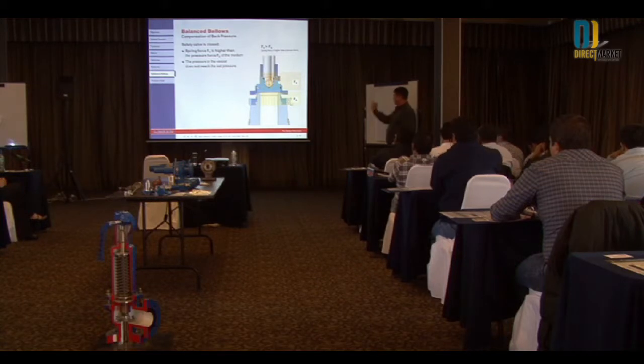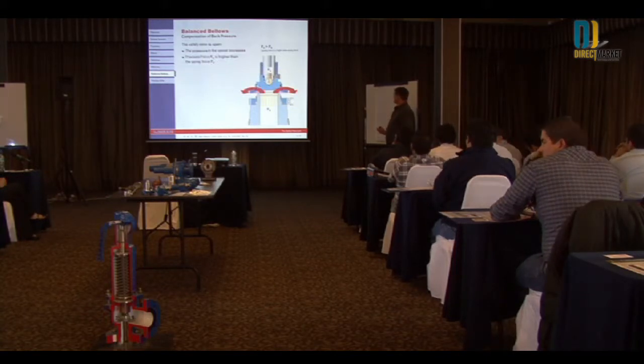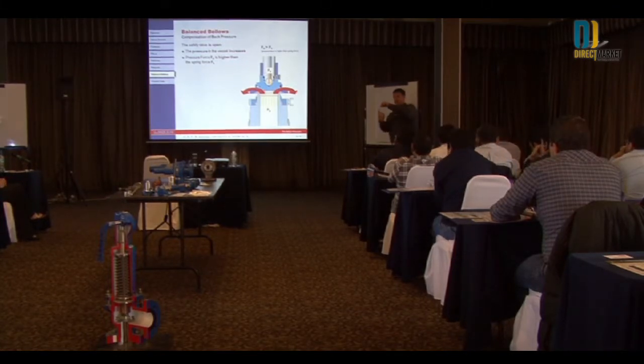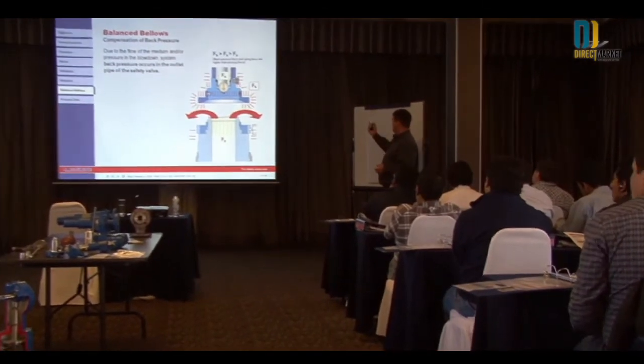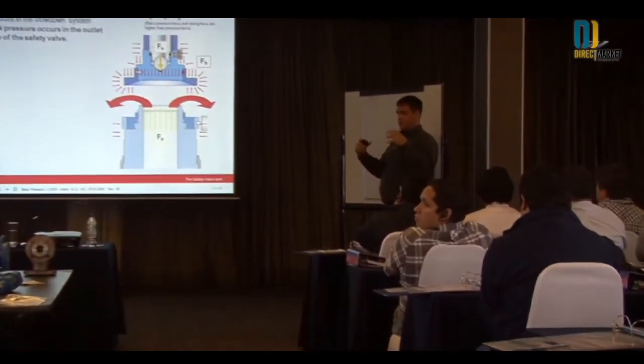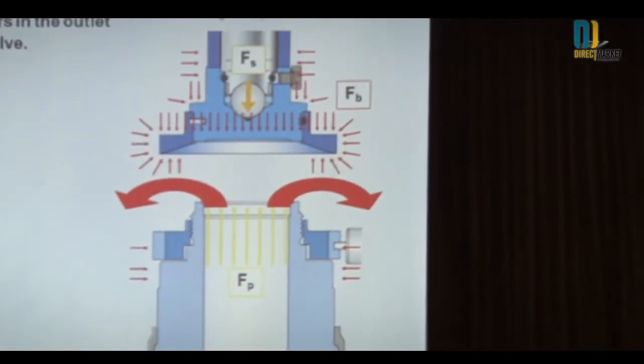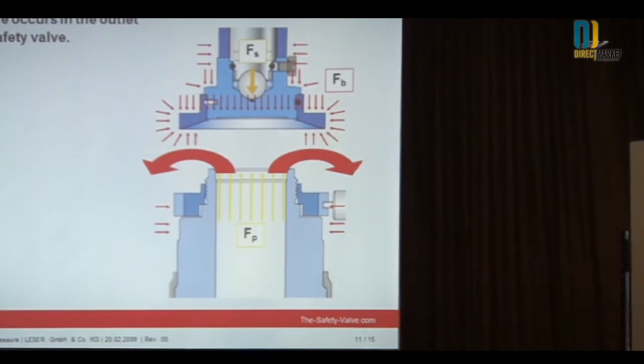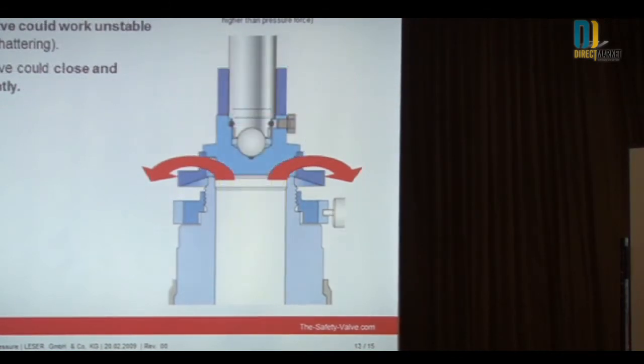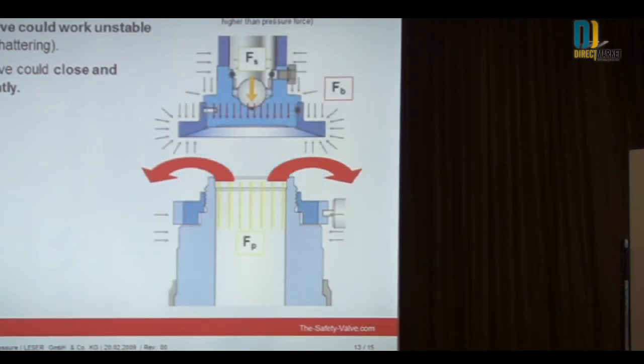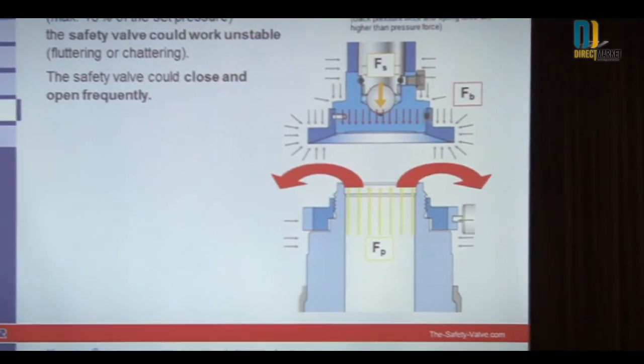This diagram shows the valve closed with pressure equal from the spring and the inlet pressure. The valve starts to open when forces at the inlet overcompensate the spring. Without a bellows in a conventional valve, the red arrows represent the influencing pressure pushing down on the disc, spindle, and internal components — most arrows are pushing down on the disc. If back pressure is too high — maximum 15% of set pressure — the safety valve could work unstable, fluttering or chattering.